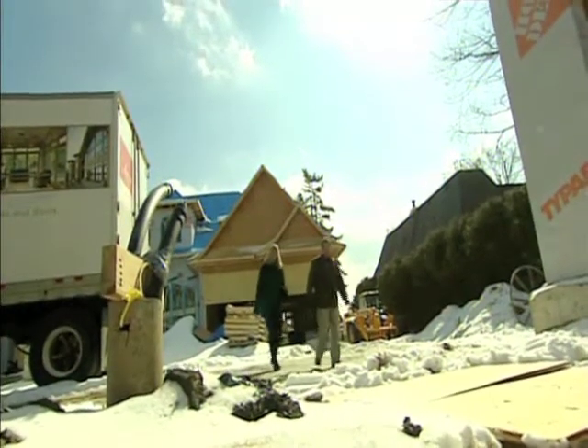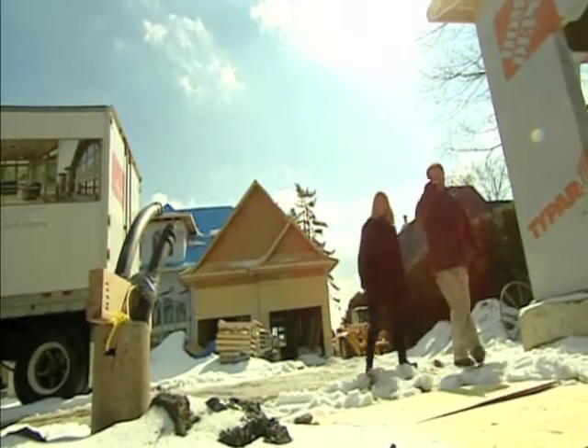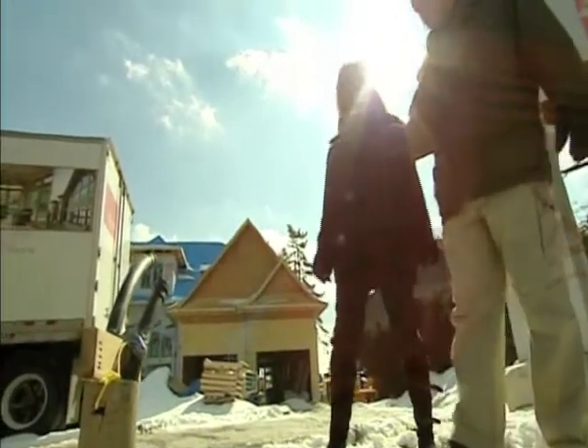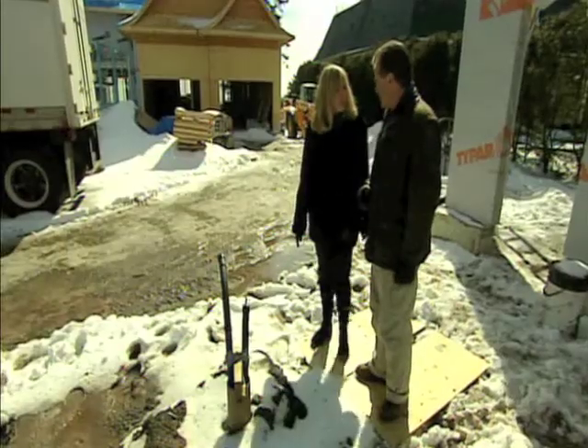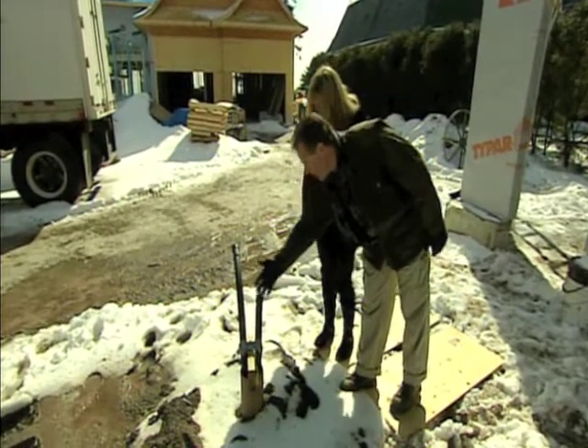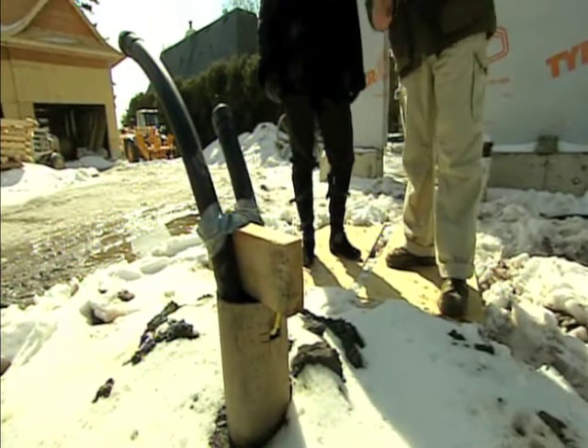These pipes here will eventually be connected. There are several ways to install a system, but in cramped city spaces it's usually done with holes drilled into the ground. There'll be nine holes here — this one is 250 feet down. Down the holes they install pipes, which will be filled with a liquid, usually water mixed with ethanol. Those pipes are connected to a heat exchanger inside the home.